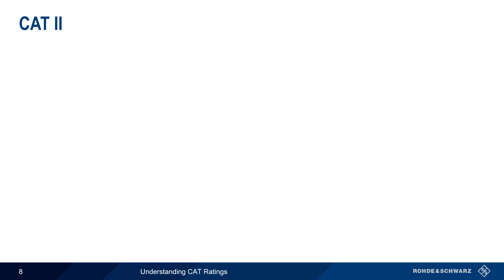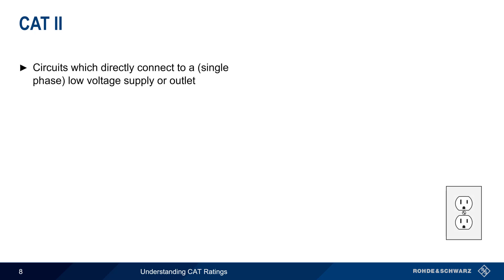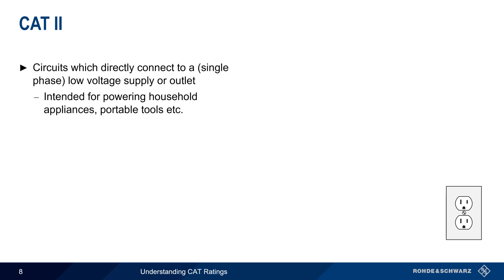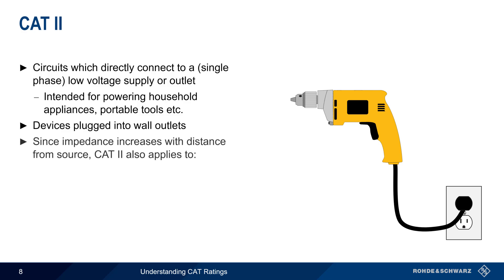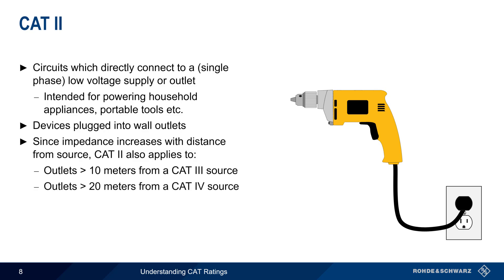CAT 2 applies when making measurements of circuits that are directly connected to a single-phase low-voltage supply or outlet. These outlets are intended for powering common household appliances, portable tools, etc. This category also applies to the devices plugged into these wall outlets or sockets themselves. Note that increasing distance from a voltage source means increased impedance, and thus a lower danger. So CAT 2 also applies to outlets that are more than 10 meters from a CAT 3 source or more than 20 meters from a CAT 4 source.